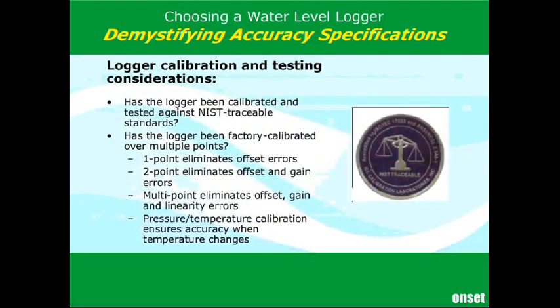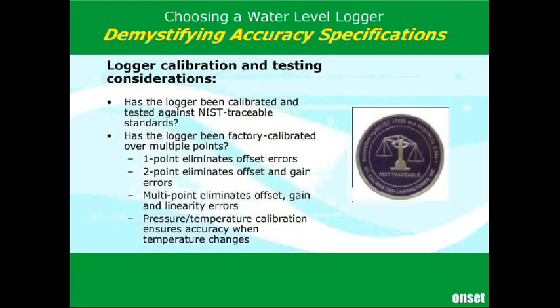Another aspect to consider is finding out from the manufacturer how the logger is tested prior to production and before it ships to you. Some manufacturers may test only one point to ascertain that it's functioning properly. However, we feel it's important that it be tested over its full pressure range at numerous temperatures with NIST-traceable standards. One point can tell you whether it's working and correct for offset; two points can correct for offset and gain. But the multipoint test we showed earlier — where pressure is varied over the full range and the cycle is repeated at numerous temperatures — is needed to give you the confidence you require.